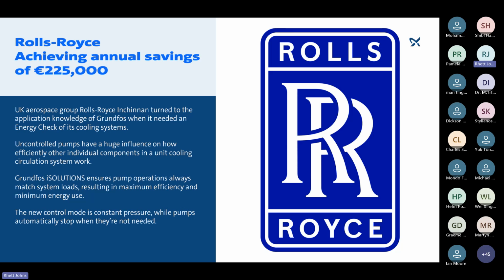And this is all done, again, with new control modes that were added to these uncontrolled pumps, and they automatically stop when they're not running. So when they're not necessarily running a set of machines, the pumps switch off. No need to run coolant through them because we're not generating any heat. So that's the holistic approach that you can get and the savings that you get on a site like this.